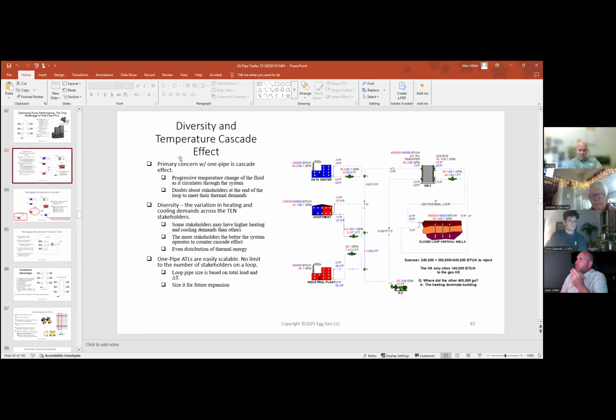One of the primary concerns that we have with this type of design in a one pipe system is something called cascade effect, which is the progressive temperature change as somebody adds heat or takes heat out of the loop. But as you can see here by these annotations, in the summertime, it's coming out designed for 65, right? Then it goes into this guy who's heating dominant. You're getting thermal mixing in this loop as the water moves through it. So it's actually going in at about 56. It's coming out at 36. But then as it gets to the next guy, look, the temperature starts to rise, and as it continues down the line, it continues to rise even more until, look, it's going into the data center at 65. Well, 65 is where we started out. And this system is designed to go in at 75 degrees.